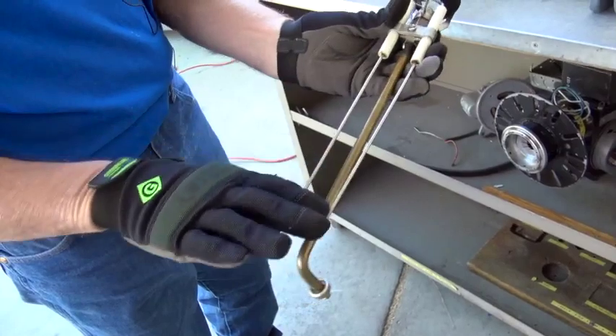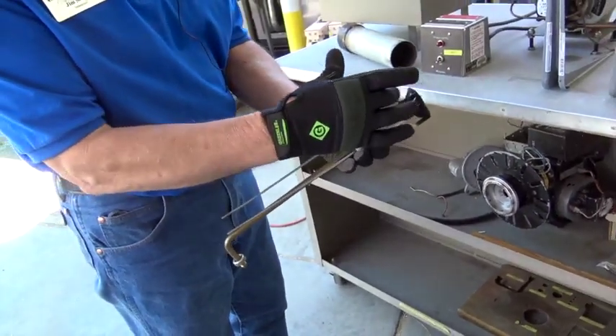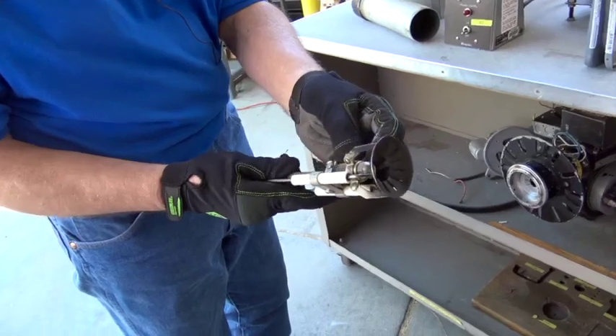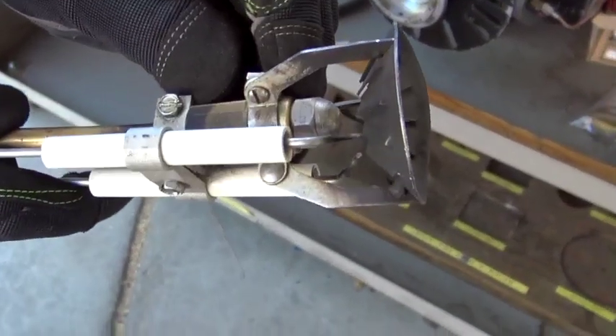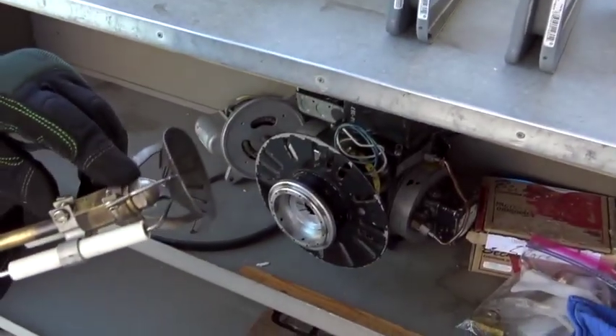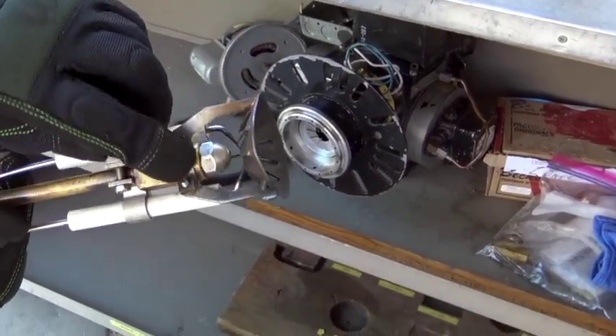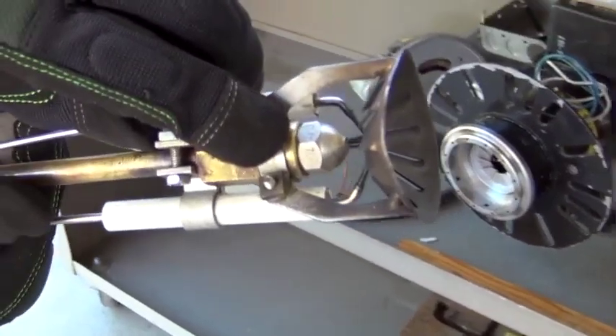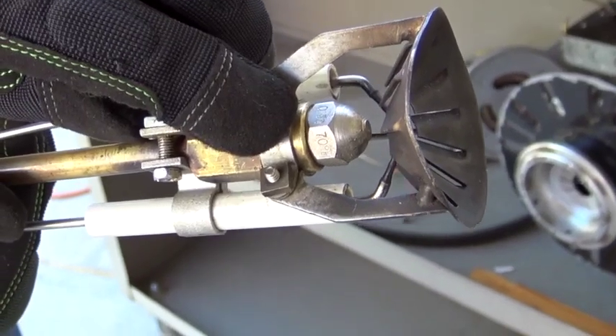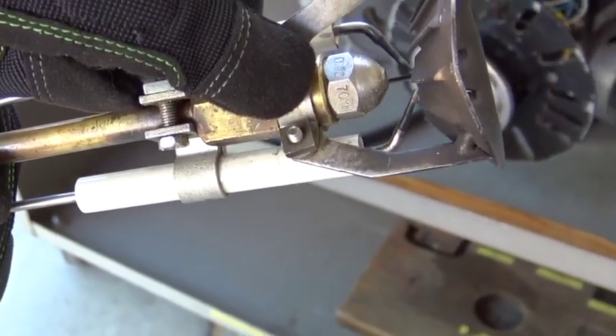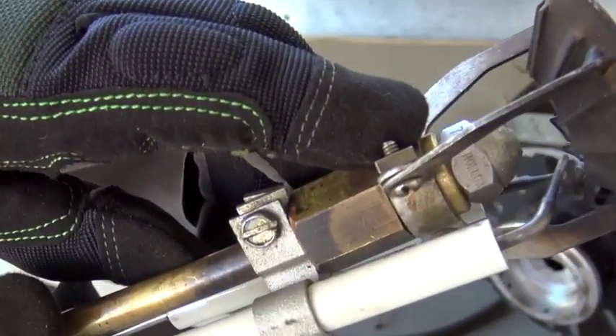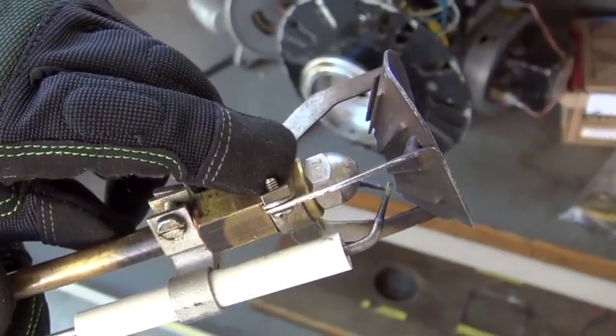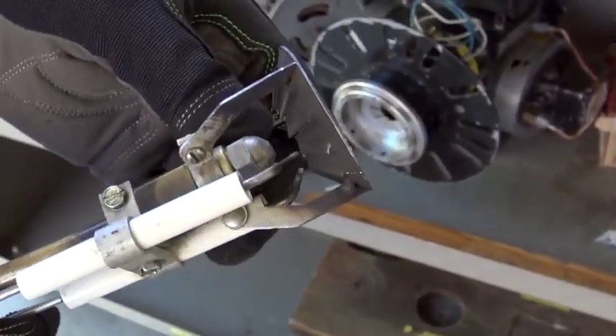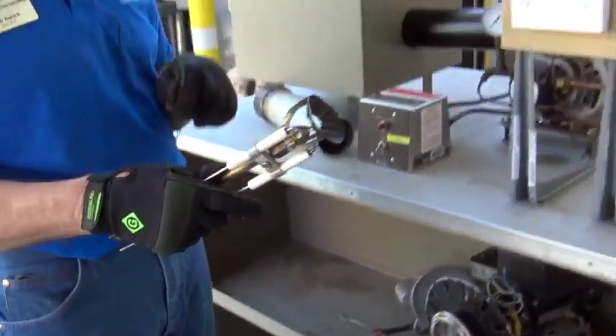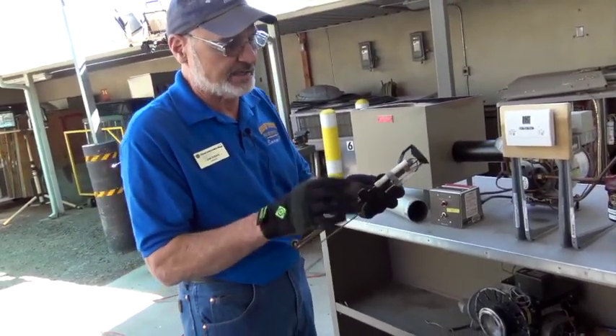This is where everything takes place here. This will wear out more than anything. The nozzle here, as you can see, there are different types of nozzle. You have to use the appropriate nozzle for that burner, rated for the degree and also how many gallons per hour. That's a 0.50, half a gallon per hour, with the 70-degree. See where it says 70, and it's a hollow cone. Remember the 3 types of cones: semi-hollow, hollow, solid.